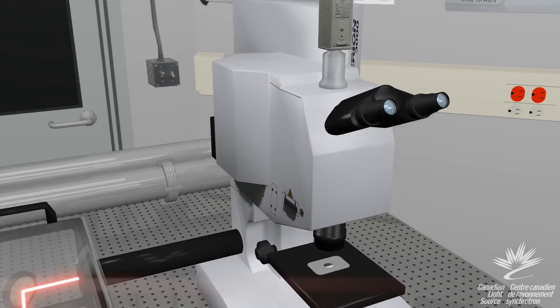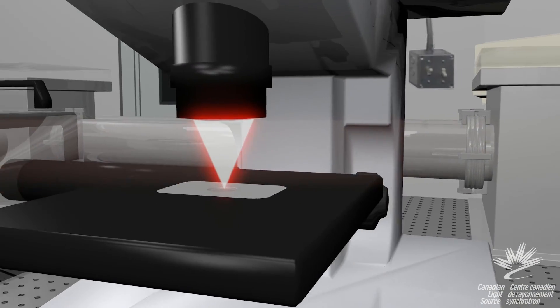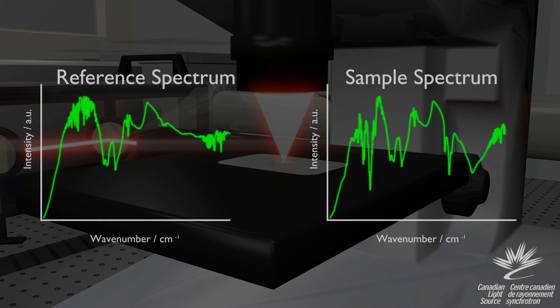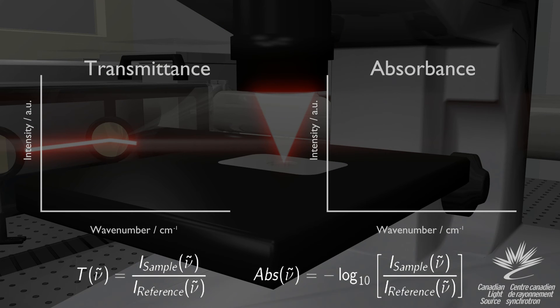The infrared light is directed from the spectrometer into the microscope and through the sample. During absorption spectroscopy, certain wavelengths will be attenuated, creating a slightly different spectrum. By dividing the sample spectrum by the reference spectrum, we can obtain a transmittance spectrum which shows which wavenumbers of light are attenuated and transmitted through the sample.